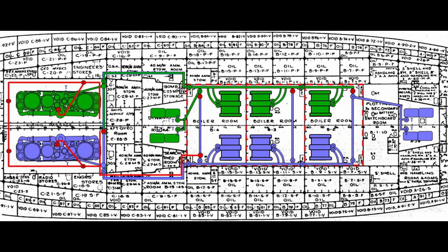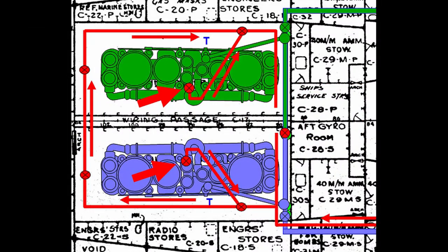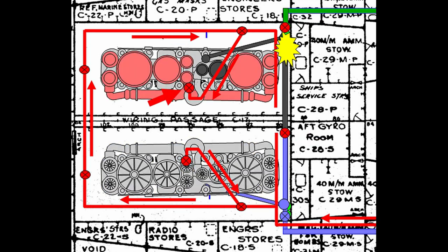Auxiliary devices receive their steam by tapping into the 300-pound cross connects in the boiler rooms. Engine room auxiliaries receive steam through a line from boiler room 4. Some is also received by tapping off steam from the receivers that connect the high and intermediate cylinders on the engines. By backfeeding into the engine's auxiliary line, 150-pound steam will bypass the main steam line, throttle valve, and high-pressure cylinder to power the engine's intermediate and low-pressure cylinders at reduced power.